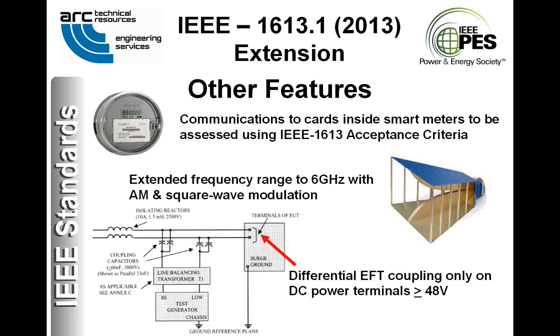RFI hazards. Clause 7.3 of the document states that the wiring needs to be consistent with the manufacturer's recommended procedures, and the EUT was tested in its case with the covers and access doors in the closed position. You would think they'd learn. Owners of installed COM networking devices, like relays or other devices that communicate, may not have been aware of the hazards that exist when these covers or doors are open.